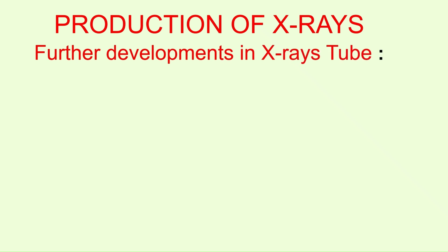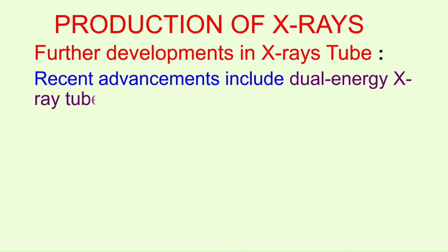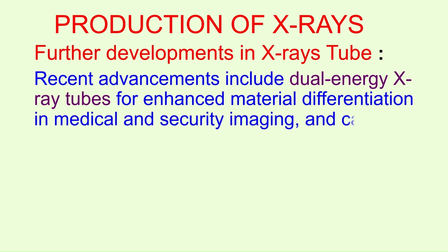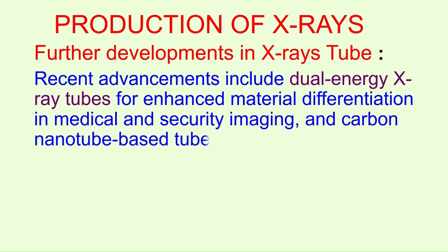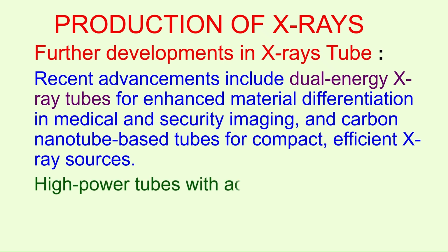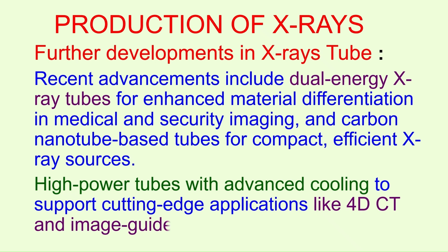Some of the recent advancements include dual-energy X-ray tubes for enhanced material differentiation in medical and security imaging, and carbon nanotube-based tubes for compact, efficient X-ray sources. Also developed were high-power tubes with advanced cooling to support cutting-edge applications like 4D CT scan and image-guided radiotherapy.